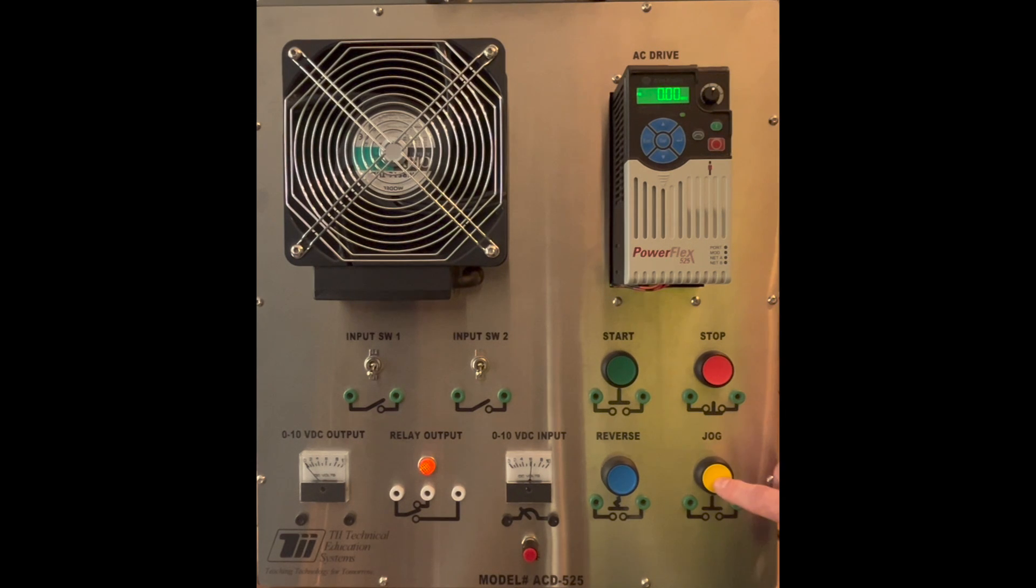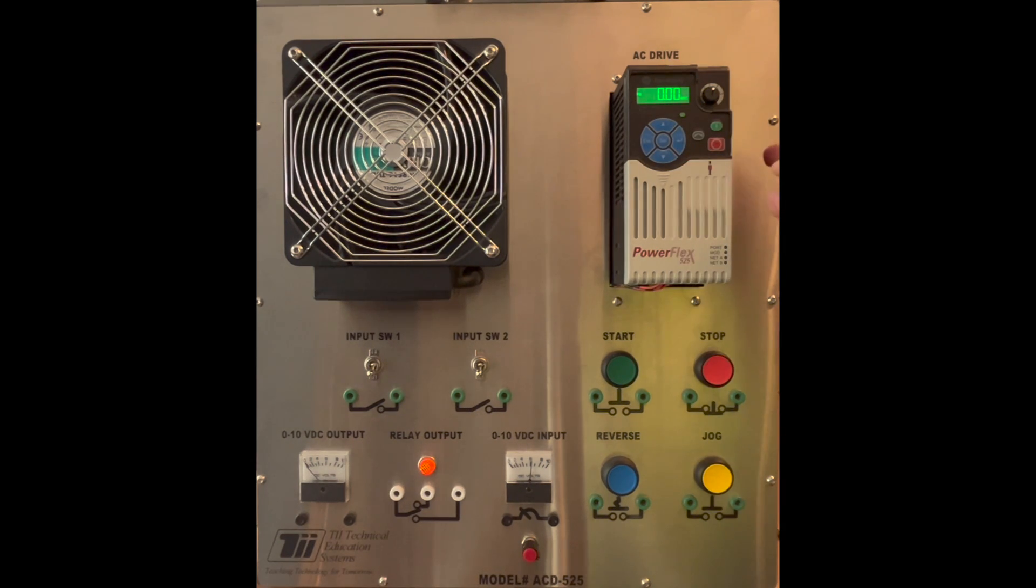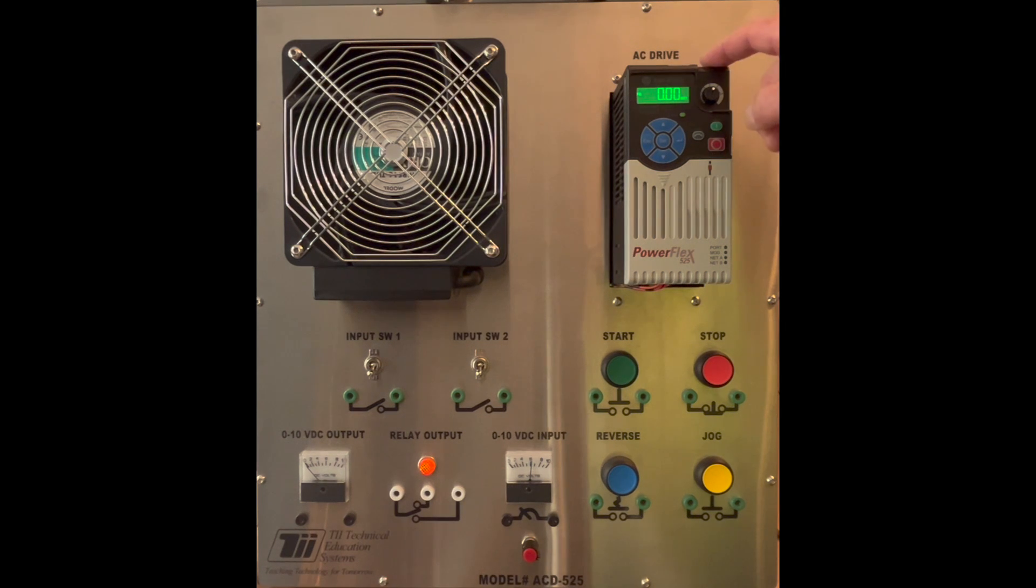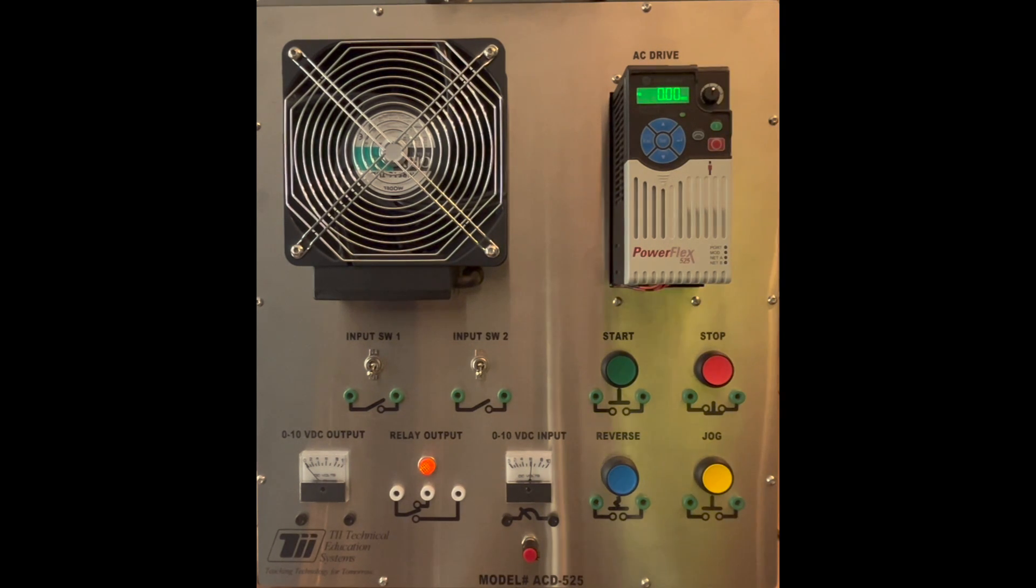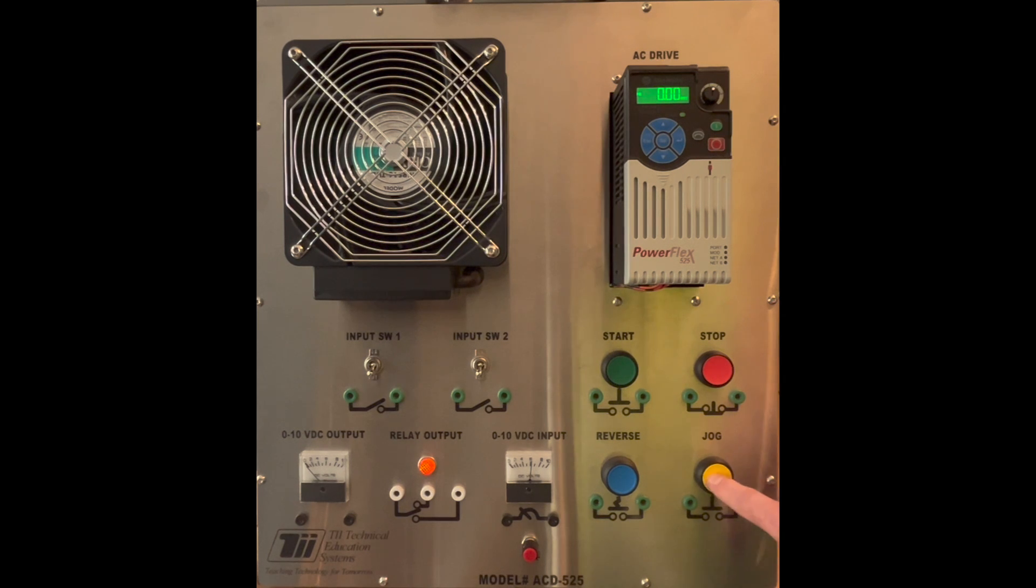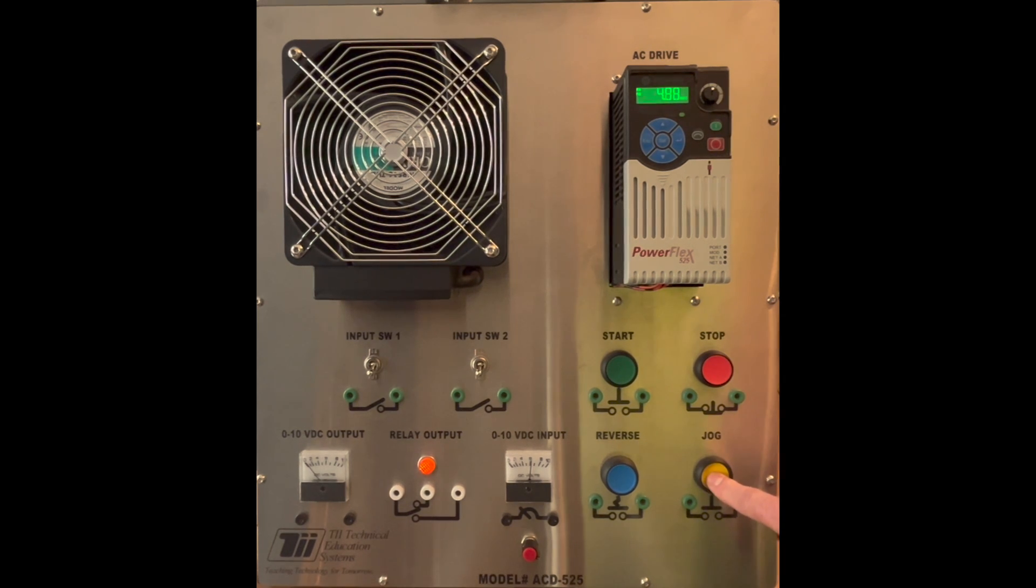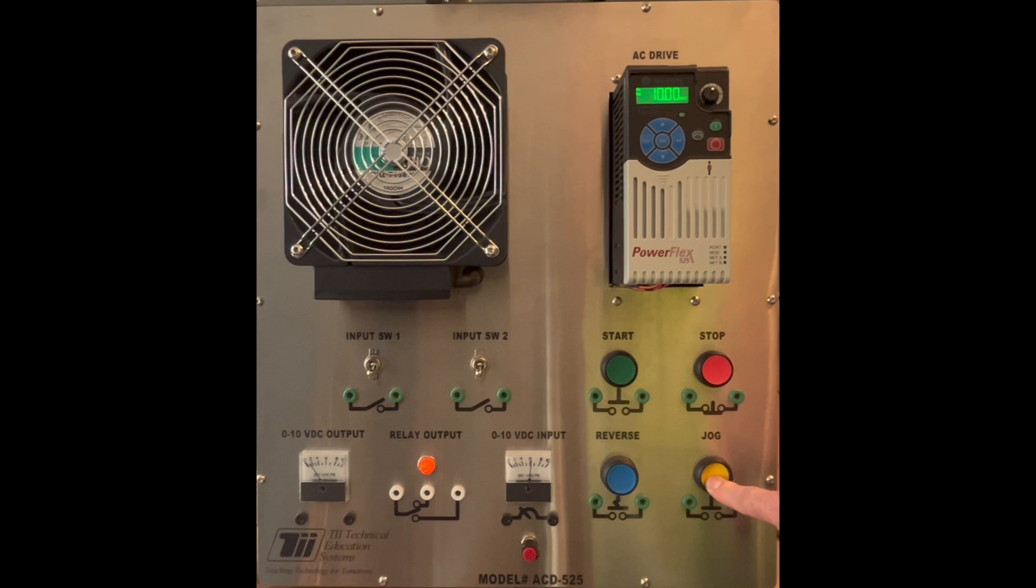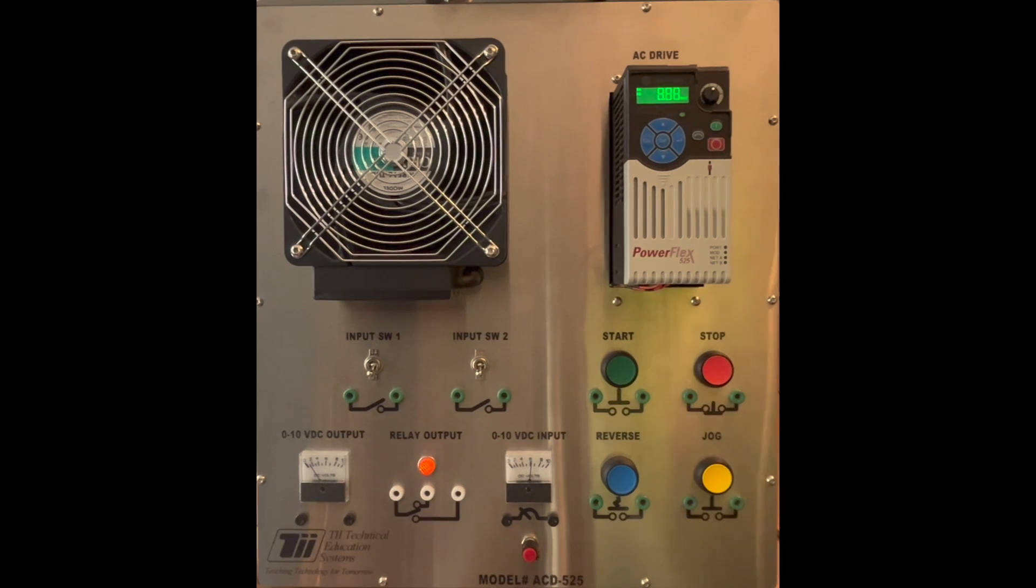The jog button will be used to jog this to whatever preset frequency this has been set to. This case comes in the factory setting of 10 hertz. So when I activate the jog button it will go up to 10 hertz. I let it go and it goes back down.